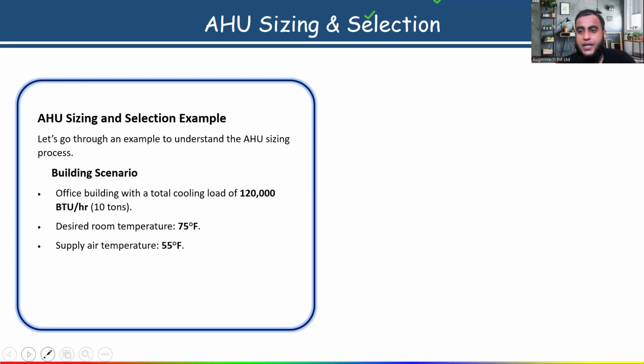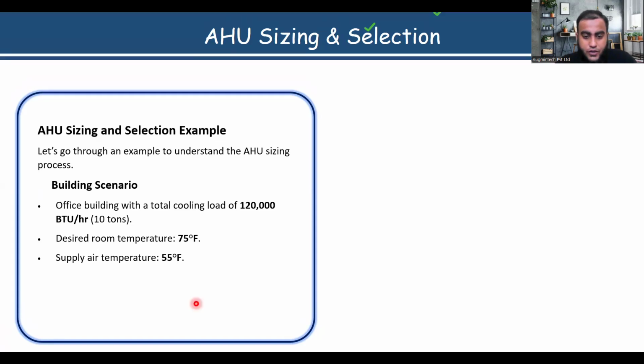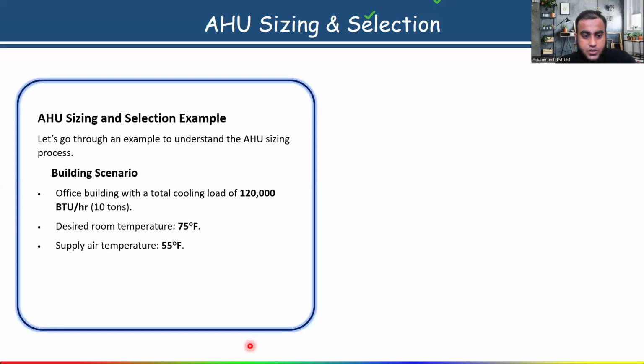To calculate the supply air temperature, remember, again I am repeating, we have a formula for that, okay? See, I will give you the example from where you will get. Actually, in manual heat load calculation, we are teaching each and everything, how you will get the supply air temperature value. Here I have considered 55 degree Fahrenheit, but from where we get this value? Maybe someone is asking me also, I think. So see, I'm showing here. Just wait, give me 1 minute. So we'll show you that.